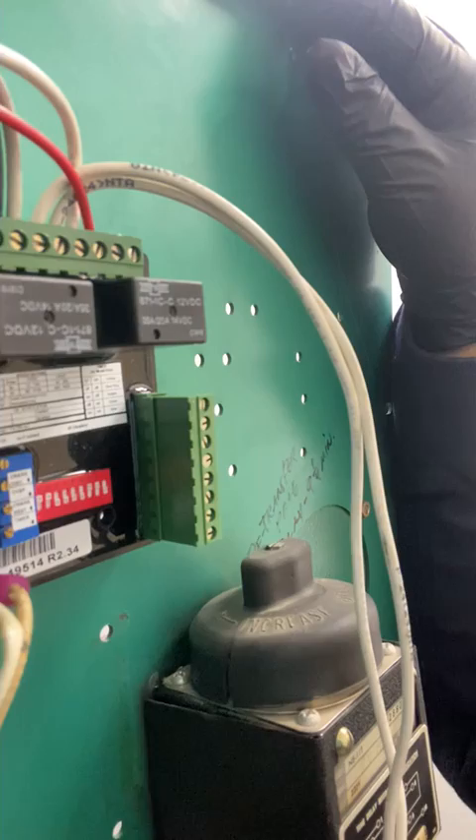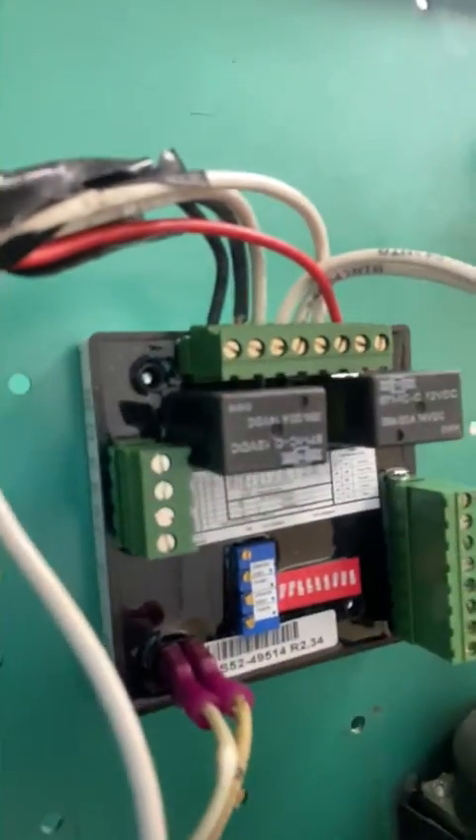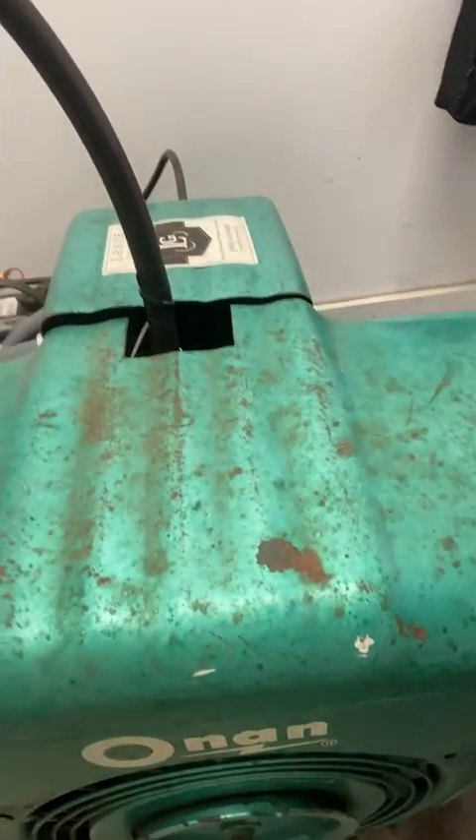So yeah, it's a pretty neat little controller. You can use them in a lot of different scenarios, and this one happens to be used to run this little Onan 5KW generator. We got the new one installed, tested, everything set correctly, and now it's just a four-hour load bank. All right, have a good day.